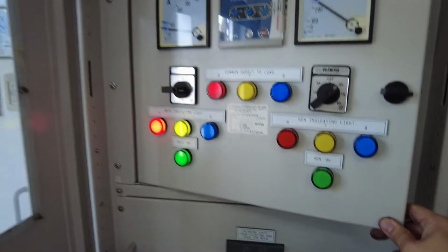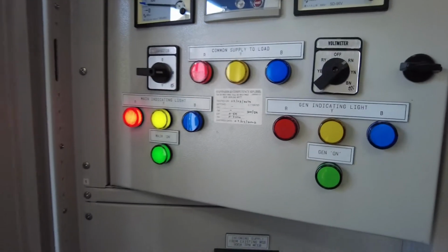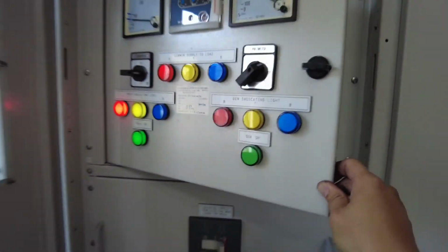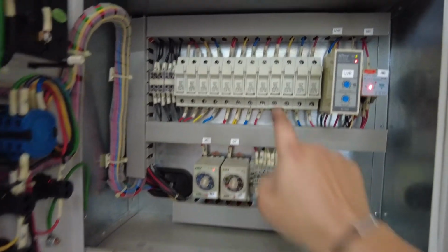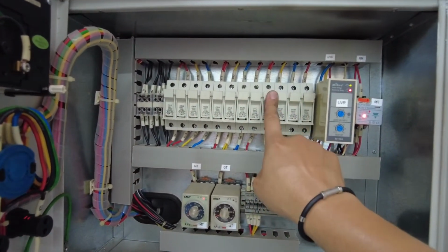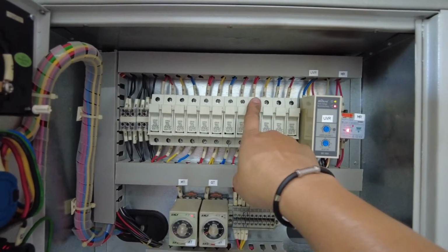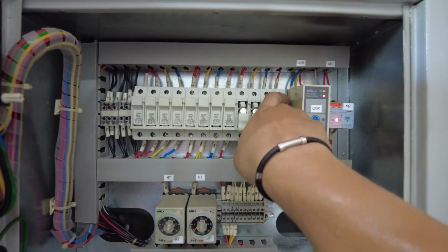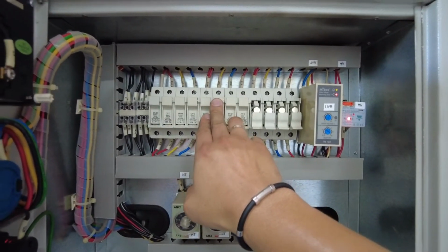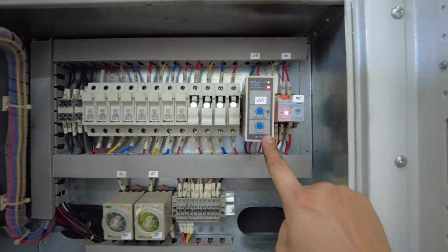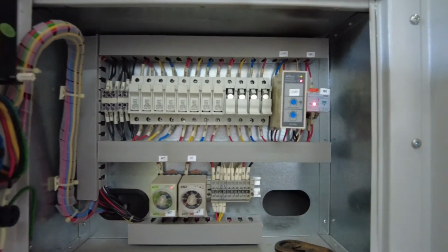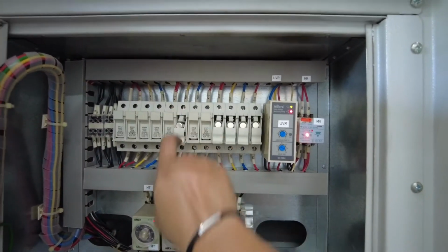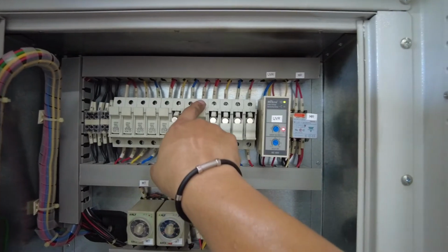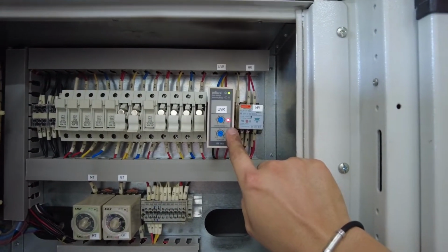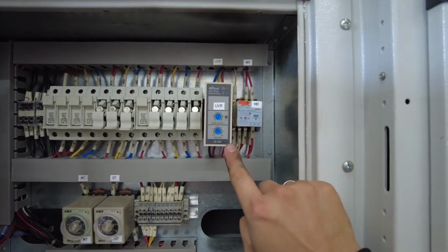Now it's under auto mode. Okay, now I'm going to use another way to simulate TMB power interruption and to test run the genset under auto mode. Okay, here we have the genset power supply. This is the control fuse. First of all, I take out the genset supply control fuse first. Then I'm going to take out the UVR control fuse to trigger this UVR relay so that it can call the genset to run under auto mode. Okay, it's triggered already. Okay, the genset is running.